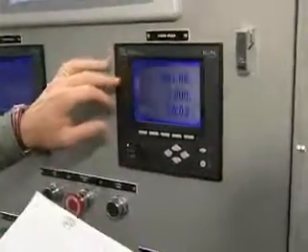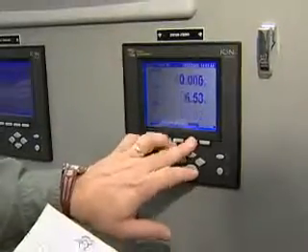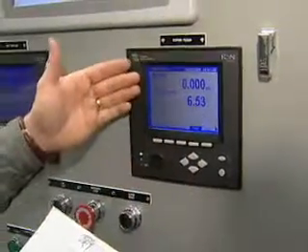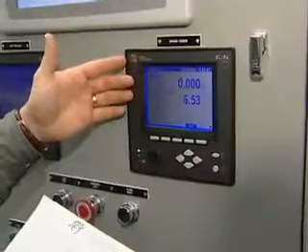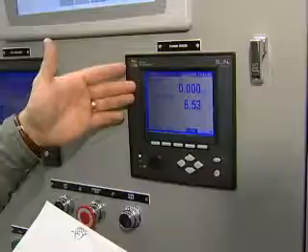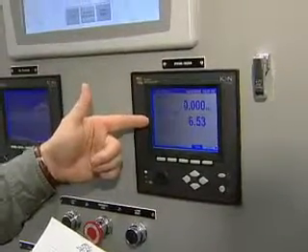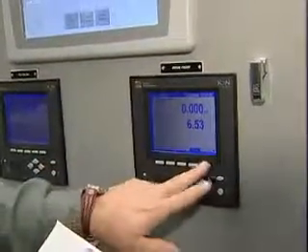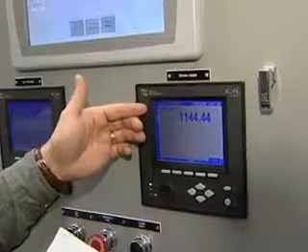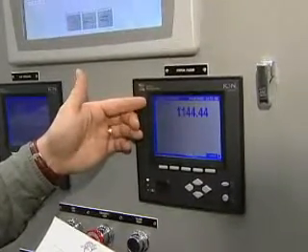You'll do the same thing with the station service meter. It's got volts, amps, and frequency. You push the power button and it comes up with your total KW that your station service is running at and the maximum peak that it's ever run at. You go to the energy button, and this one gives you your total KWH for the station service.